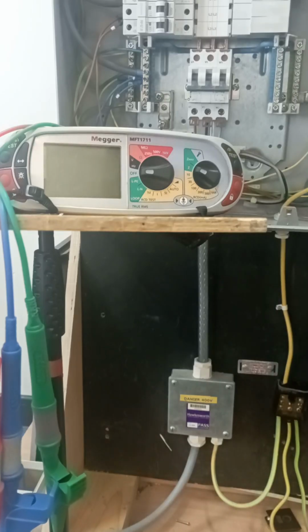Okay, now that we're ready to move on to the rest of our live working at the origin of the supply, we're going to have to disconnect the earthing conductor going into the main earthing terminal down here, so that we can carry out a ZE test on the installation.